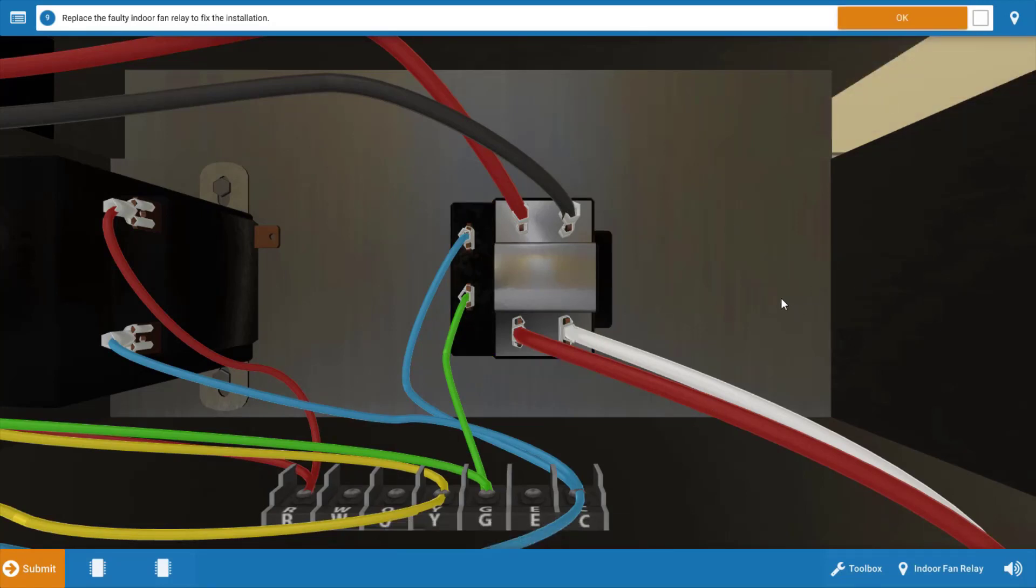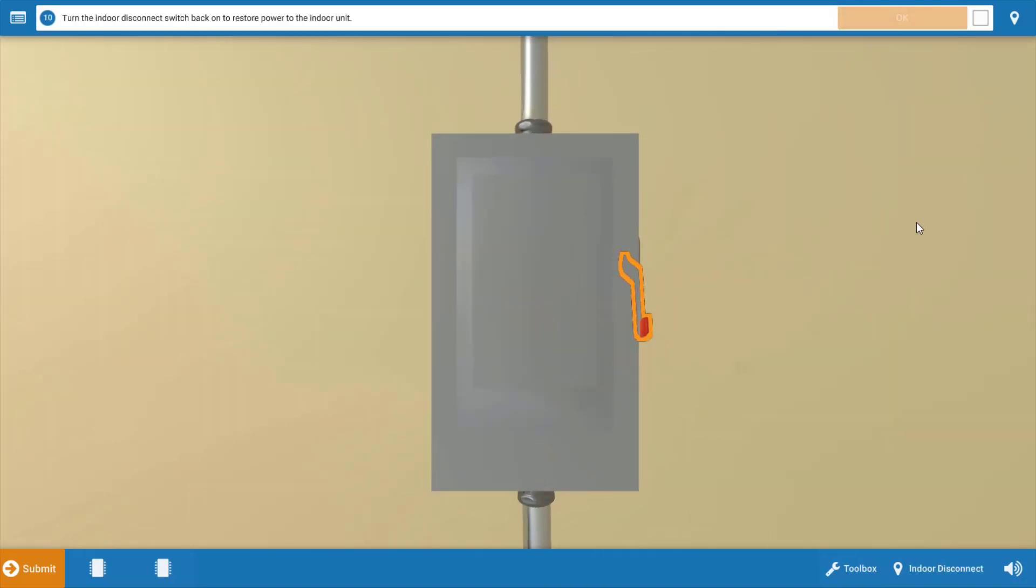Now, I strongly recommend you watch one full cycle of operation. In fact, you may need to thaw the coil out because without this indoor fan running, you're going to accumulate a fairly good amount of frost on that indoor coil. And you may need to defrost that with a heat gun or running the blower for a while to defrost the coil. After that, make sure everything's running properly and then go up in the space and verify that cold air is actually being received.